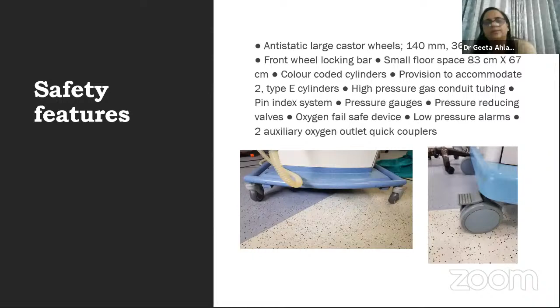Then there is the color coding of the cylinders, provision of 2 cylinders on each machine, pin index, pressure gauges, as we've all said, and oxygen failure devices. There are 1 or 2 auxiliary outlets, depending upon the make of the machine, so that you can nebulize your patient, give an extra oxygen supply, or use it for attaching a Bain circuit. Nowadays, we are attaching the Bain circuit to the auxiliary outlet, to the alternative supplies.